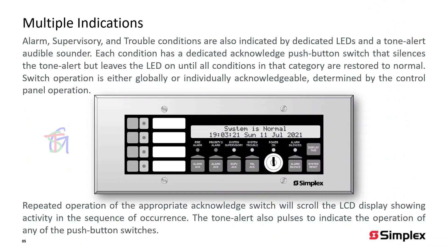Alarm, supervisory, and trouble conditions are also indicated by dedicated LEDs and a tone alert audible sounder. Each condition has a dedicated acknowledge push-button switch that silences the tone alert but leaves the LED on until all conditions in that category are restored to normal. Switch operation is either globally or individually acknowledgeable, determined by the control panel operation.